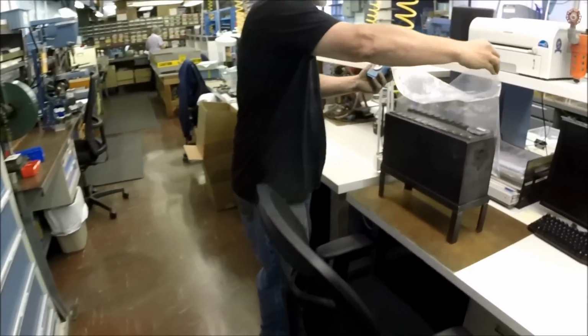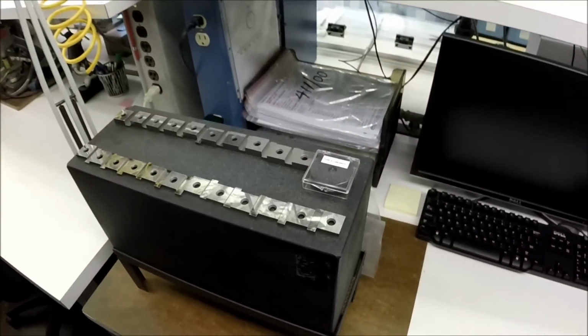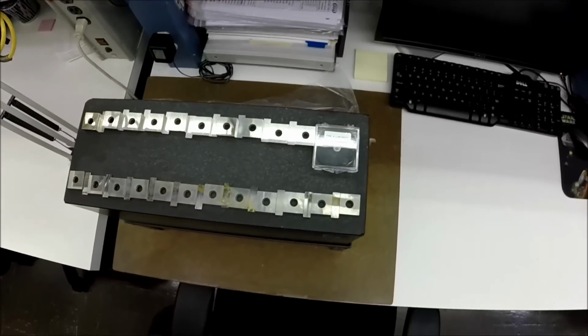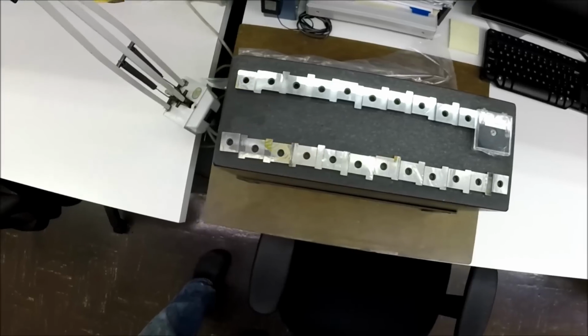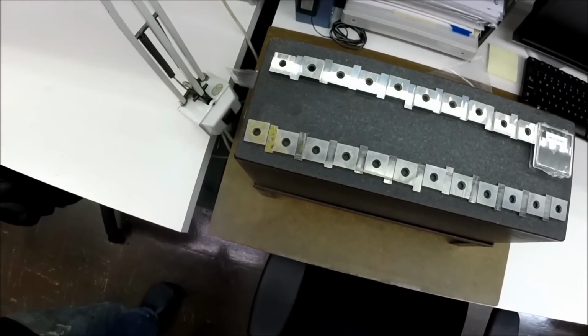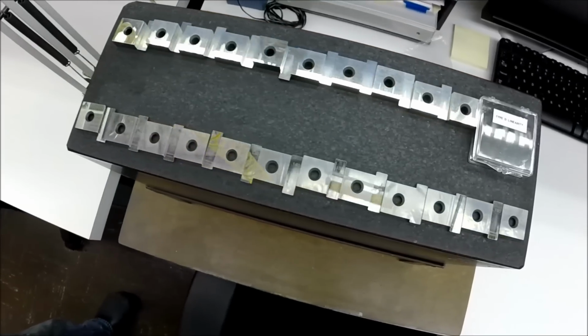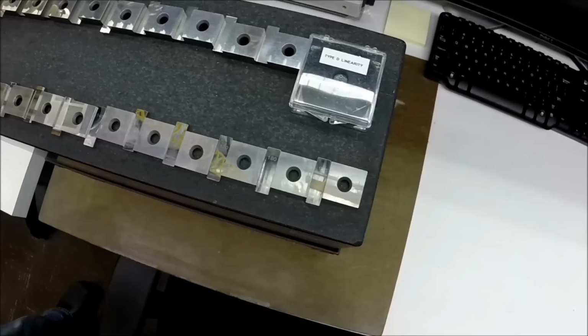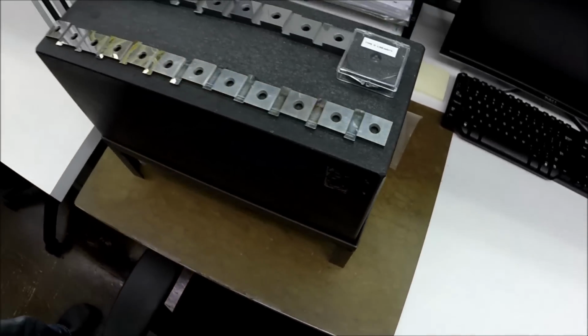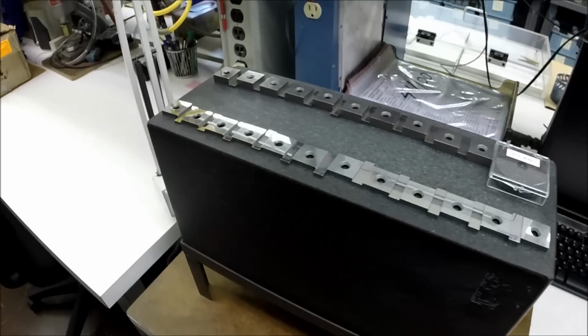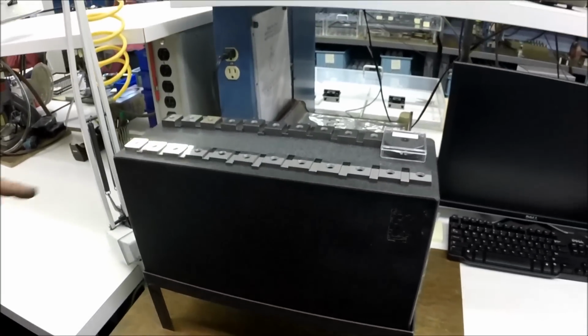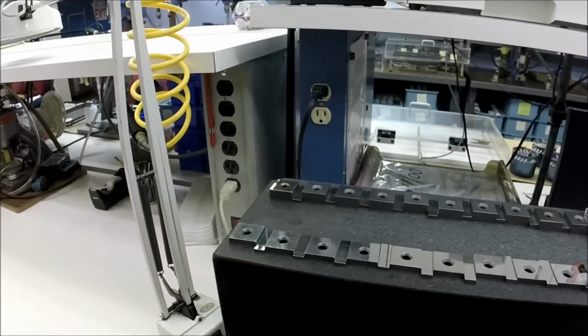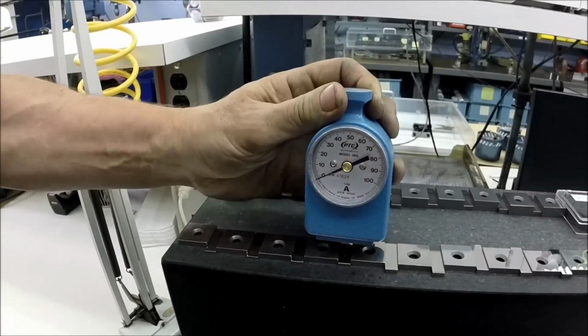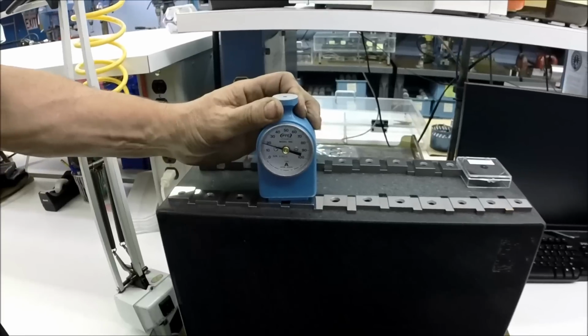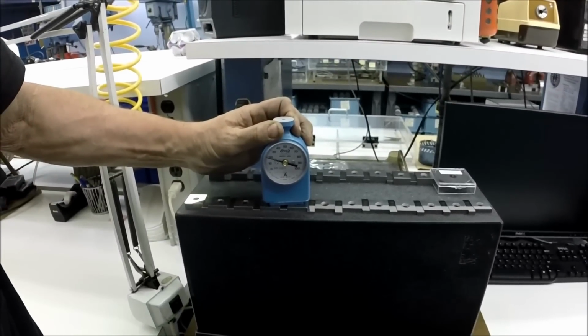Down here is a full set of calibration blocks to check the durometer. What the calibration blocks are for is to check that the dial indication on the durometer is linear every 10,000ths of an inch. It would not make a good instrument if it didn't read the correct relationship between the extension of the indenter and the dial reading. So typically the durometer might be placed between two of these blocks, and it tells you the extension and whether it needs adjustment or not.